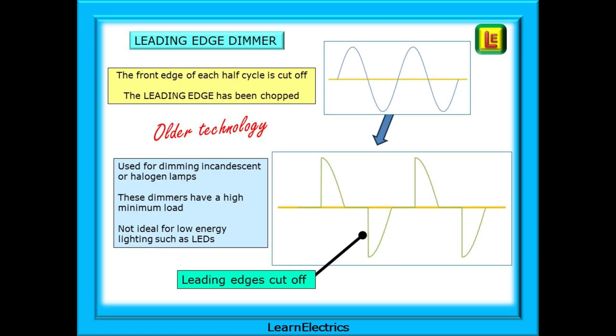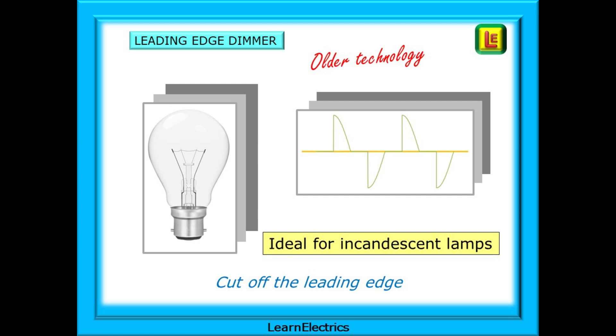Older technology dimmer switches are still in use today, and they are what we call leading-edge dimmers. The front edge of each half cycle is cut off — the leading edge has been chopped off. This type of dimmer switch is used for dimming incandescent or halogen lamps, and the type of technology used means that these dimmers have a high minimum load, and as such, they are not always ideal for low-energy lighting such as LEDs. Leading-edge dimmers will chop off the leading edge. This simpler-to-manufacture technology is ideal for incandescent lamps, as we shall see.